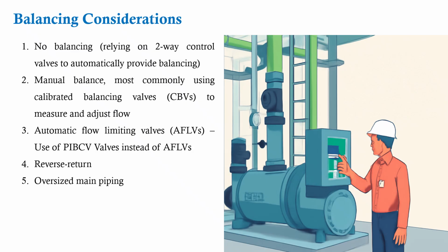The oversized main piping, how it really adds value, or how it is adversely impacting the performance of the system, or undersized branch piping actually. If somebody has an undersized branch or piping to balance the flow, instead of putting the valve, can I reduce the pipe size to ensure that minimum flow is going to be there to the AHU or any particular zone of the building? Undersized control valve, how undersized control valves also play a critical role if not properly designed.